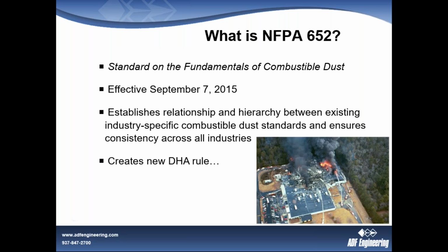This all started in September of 2015, 3 years ago, when NFPA issued the new standard on fundamentals of combustible dust, NFPA 652, which established an overarching relationship over all of the standards that had existed before. Those were standards you would be familiar with, such as NFPA 61, 654, 68, 69, and several others that cover a variety of different industries.